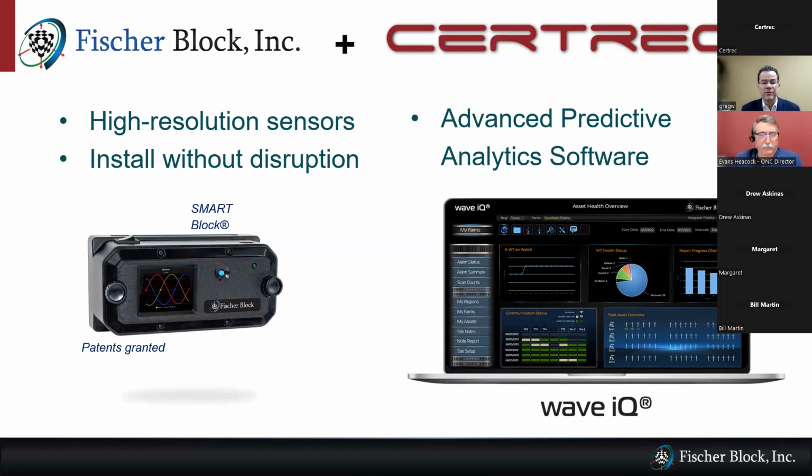What we're doing, though, is we're monitoring the electrical signals in the process, whether it be generation or delivery across a grid or consumption. And we're looking at how the electrical signals are impacted by the degradation of the assets, so that in rotating equipment, for example, as subcomponents begin to degrade in health, such as windings or bearings or gears or fan blades, they will start to actually impact the electrical signal.